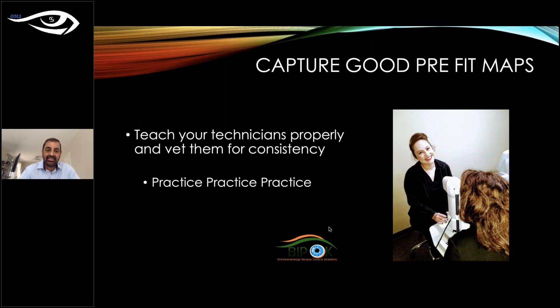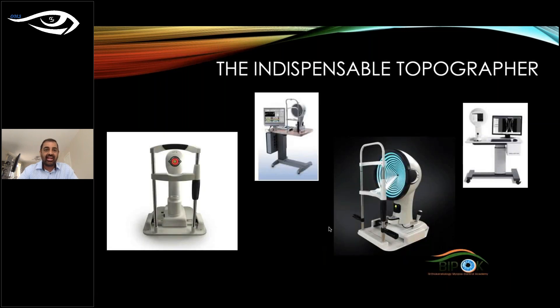Practice topography regularly — whether it is you or your staff. My routine is to take a reading of one of my staff, then measure again and check the data is consistent, which confirms the topographer is calibrated. Calibration will save you a lot of money when ordering lenses. Many topographers are available on the market. I personally have used Medmont for over 18 years — it is reliable, rarely goes wrong, and a lot of software can be attached to it for lens design.